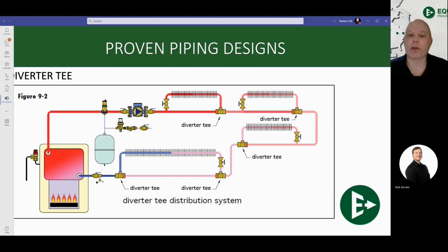Moving forward, we're going to have our diverter tees. These are also known as monoflow tees. What these are doing is forcing flow into an additional loop created off of your primary or main, usually into a radiator. Now these diverter tees are designed in a way that you see restriction on the hot side going in. As the water sees restriction going in here, it's going to force the water back up through the back side of the rad and then back down in through the tee and then on.